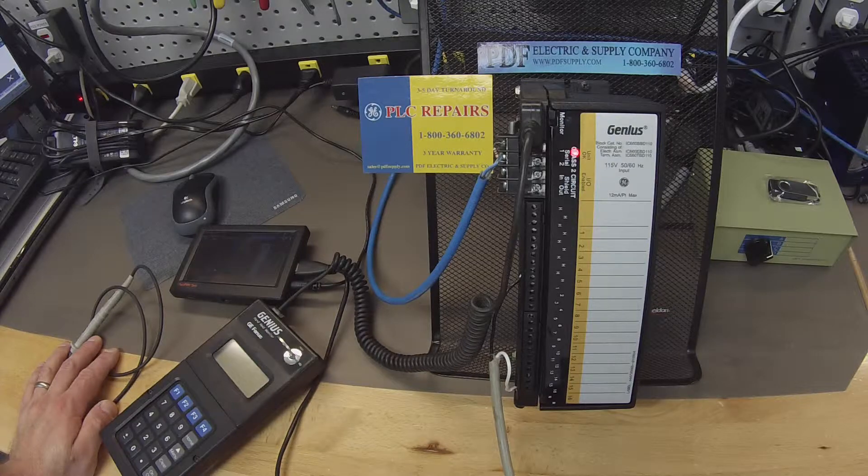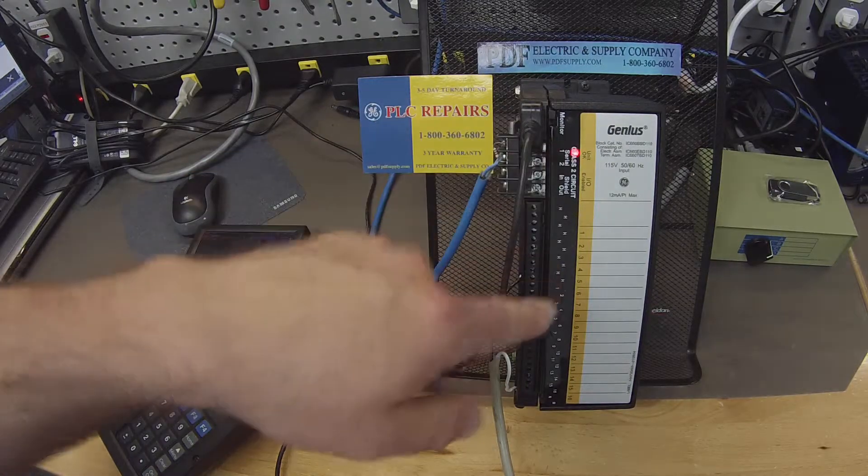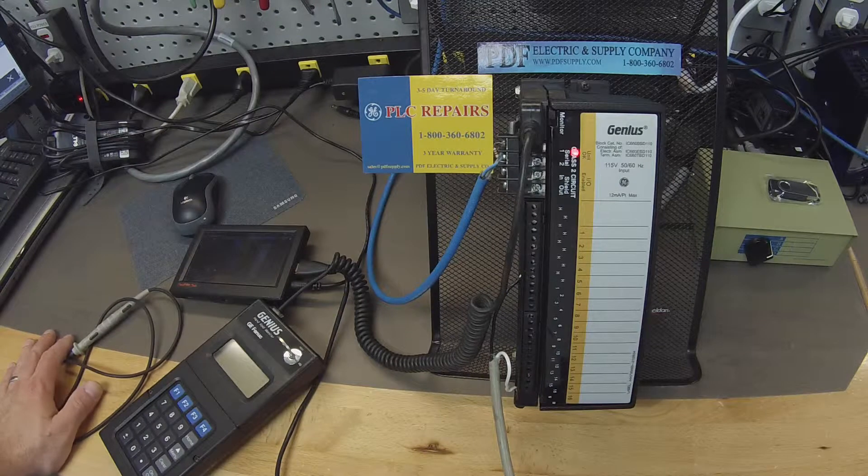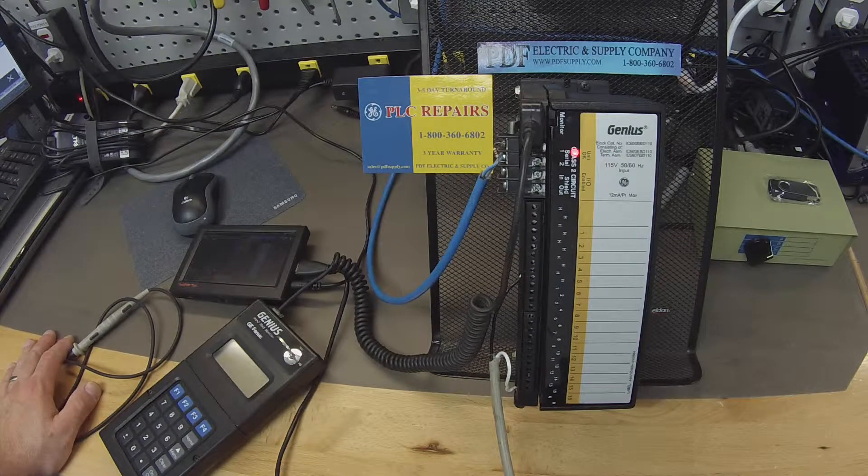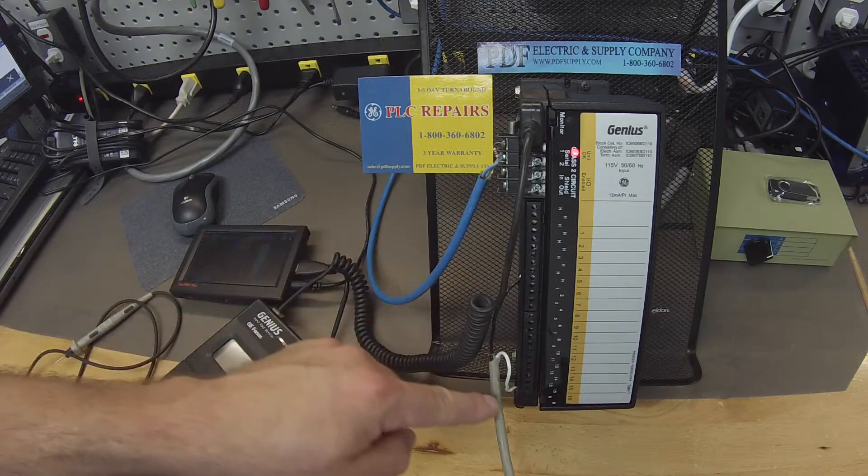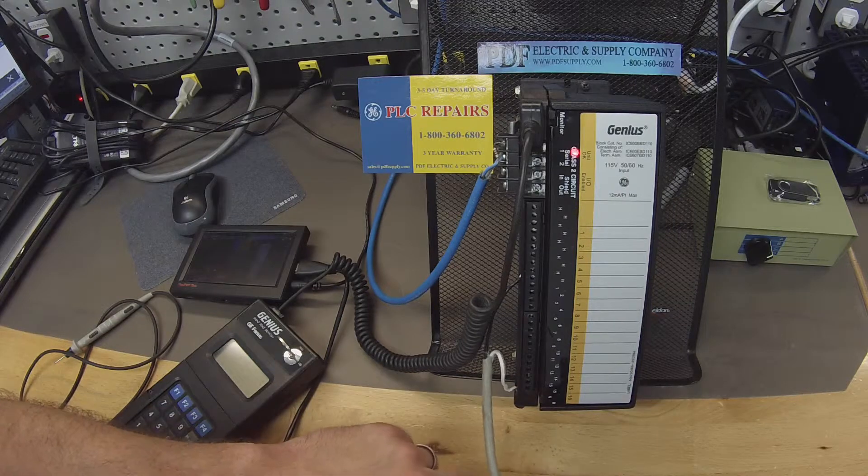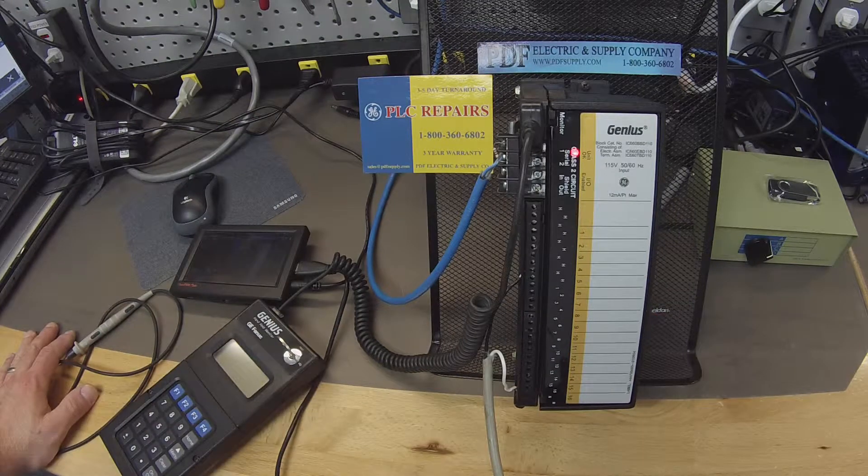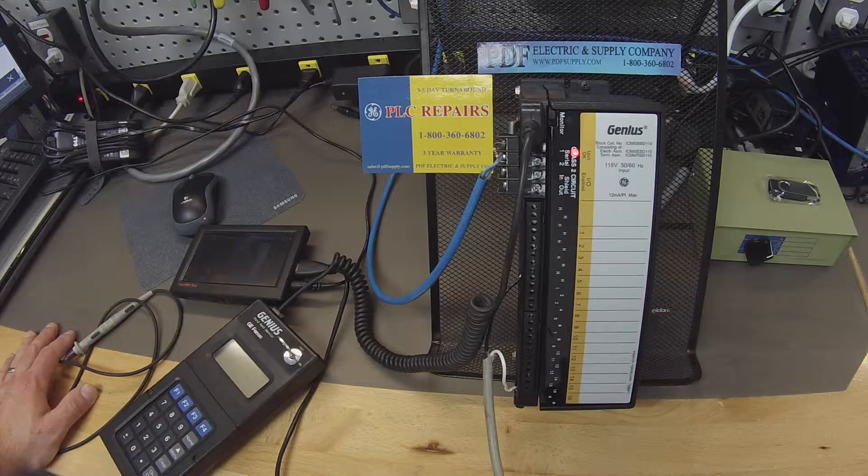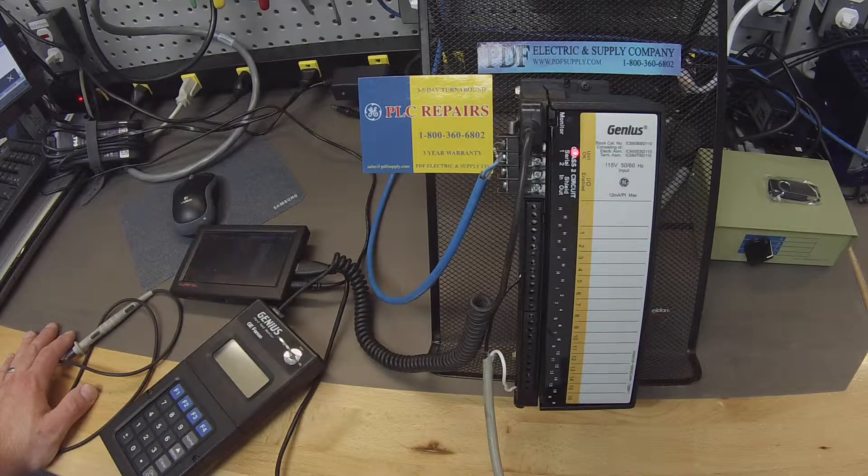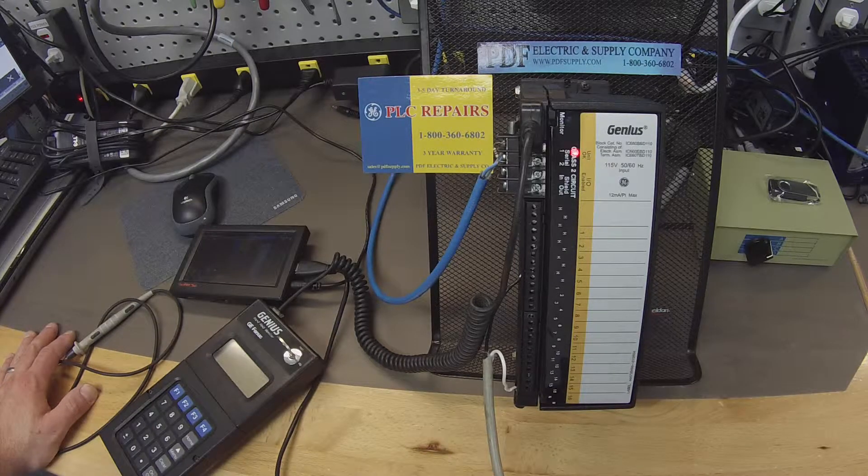The first thing that you can see in front of you is we have the block powered up and I have a solid red light. If for some reason you guys power up the block in the appropriate areas with 115 volt AC power input and you don't get a light then that obviously means that there's something catastrophically wrong with the block and it would likely need repair or replacement.